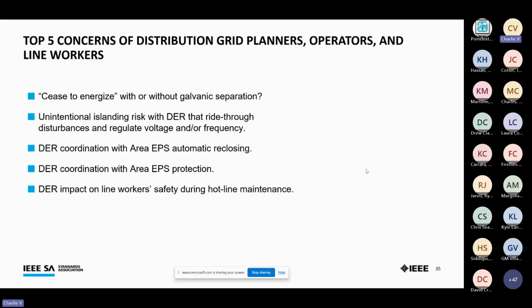So this is Rule 21, or I'll call it the 1547 working groups. When they wrapped up the update to the revision, they did a nice survey facilitated by EPRI, where they canvassed all of the working group members and other interested parties. What remained their top concerns? I'd just like to point out that unintentional islanding and cease to energize without galvanic separation, and this is relevant to you all: do you have to physically separate, open contactors, to cease to energize? There are inverter advocates who can argue really well that you can use control systems to assure you're not backfeeding and energizing a grid that is out. So those are still at the top.